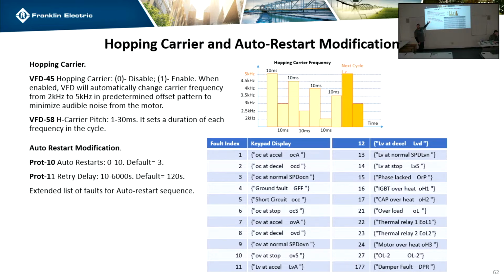It's whatever your time is multiplied by the number of tries, but you can extend the retries or shrink it. So you can go all the way down to 10 seconds. You can set it to 10 and 10, so every 10 seconds after a trip it's just trying again and again and again. But this is also tied to your fault relay. Your fault relay will not trigger until this sequence has exhausted.